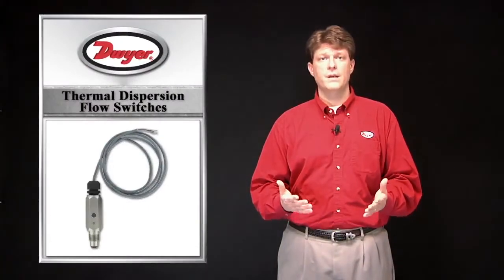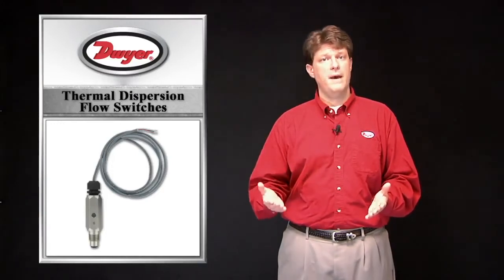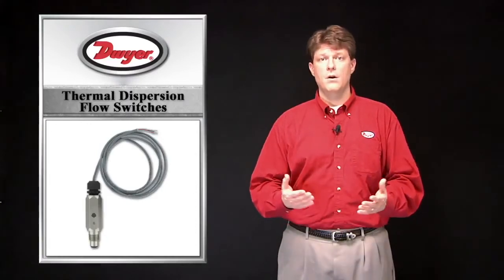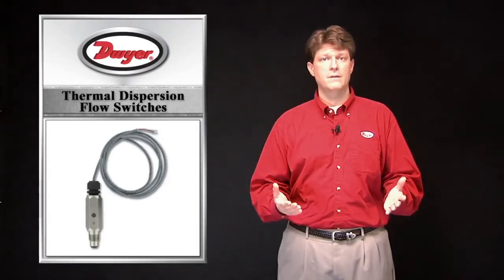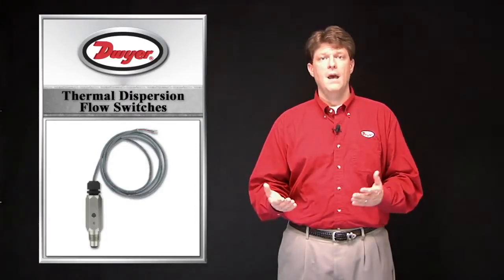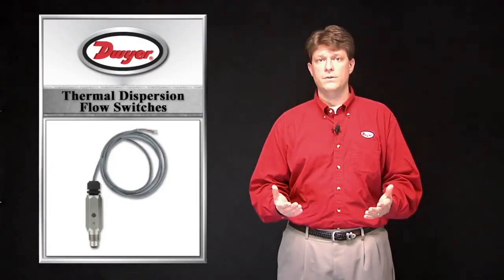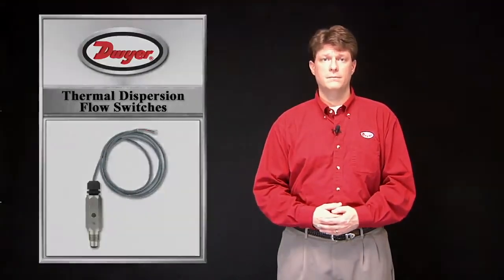Thermal dispersion flow switches have many advantages over mechanical flow switches since there are no moving parts, such as paddles or vanes, offering better long-term reliability and life expectancy. There are no moving parts to wear that could create leaks or switch failures, no parts to get jammed or stuck from particulate in the media, and no parts that can break off into the flow, causing downstream damage in pipes and valves. They are omnidirectional, offering easier installation without concerns on flow alignment. Additionally, since thermal flow switches only need to be inserted 10% into the flow, the pressure drop is much lower.